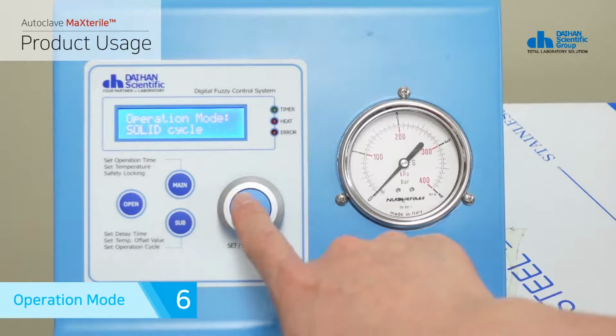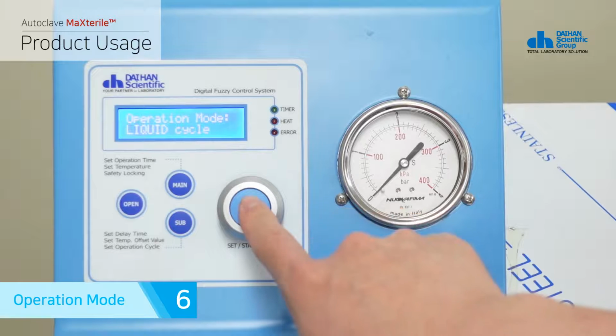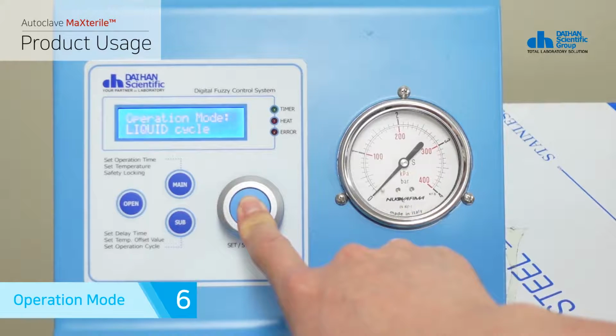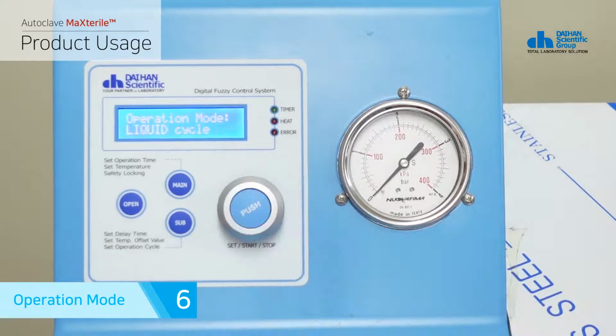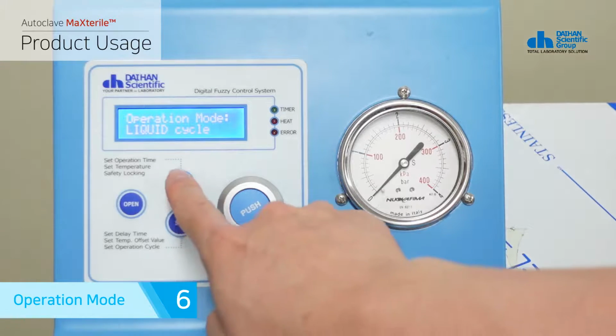This product provides liquid mode for sterilization of liquid samples. You can press the sub button in locking mode once to switch to operation selection mode, and press jog dial to select solid cycle mode and liquid cycle mode. After completing the selection, press jog dial for 2 seconds to save the mode. Liquid mode discharges steam at intervals after the sterilization process is completed, which prevents sample damage and relieves pressure slowly.